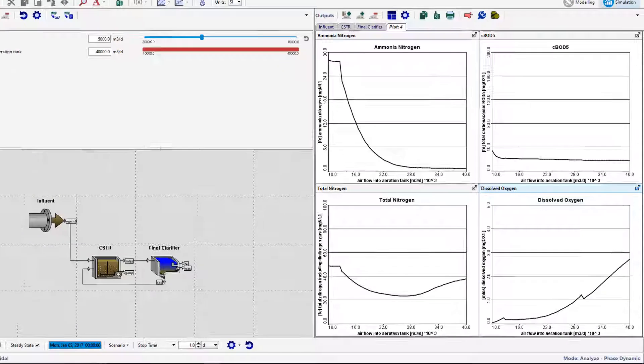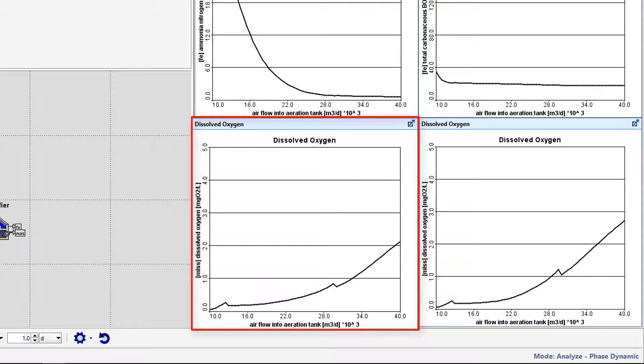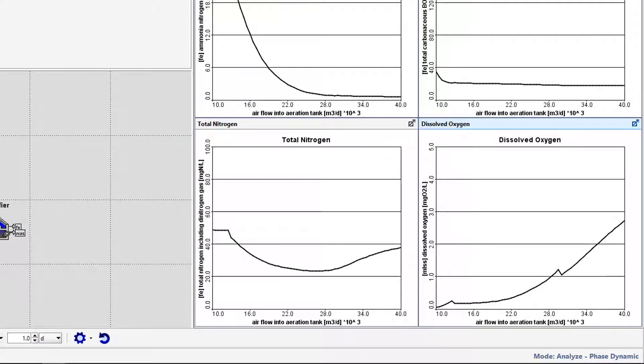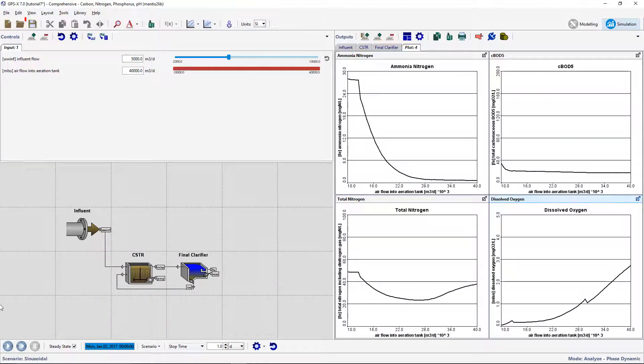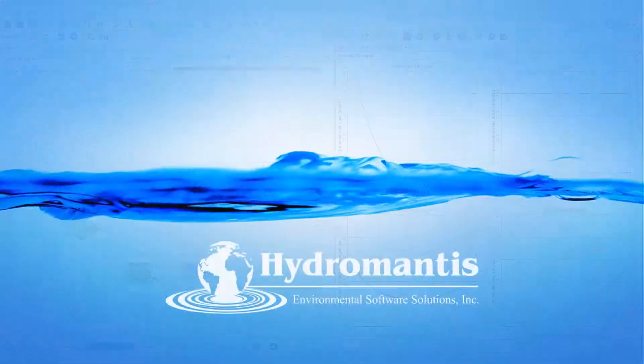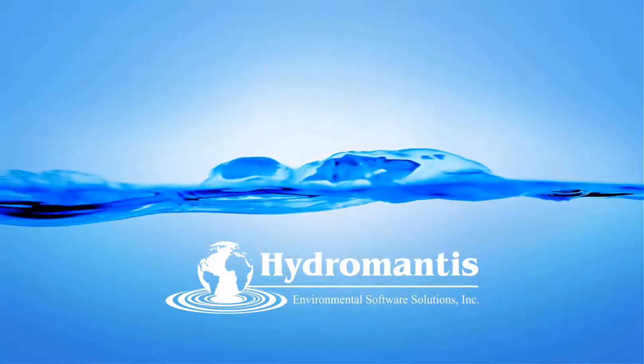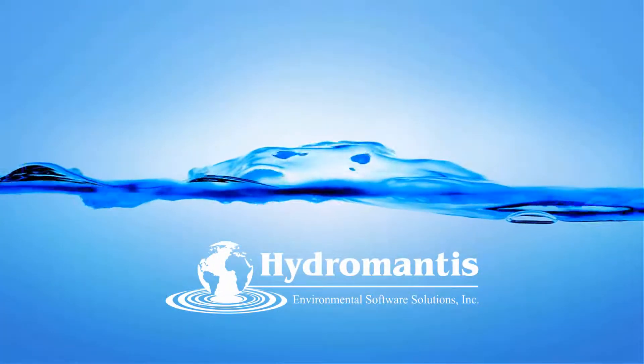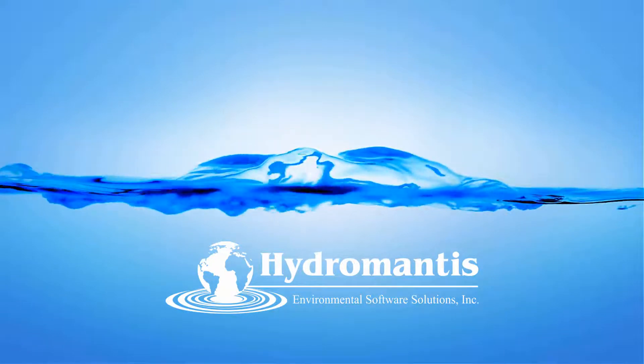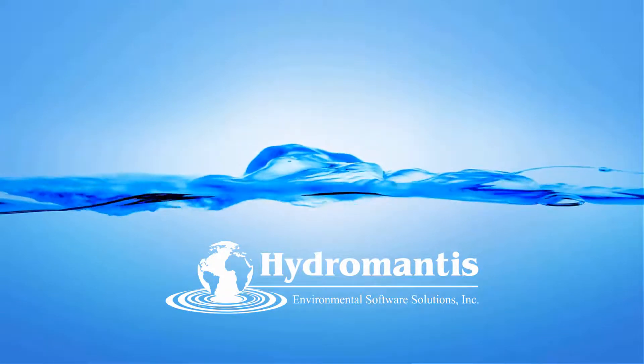This graph is only slightly different to the results presented when steady-state was selected from the Analyze menu. The graph shows the DO concentration after 1 day for an airflow of 10,000 to 40,000 m3 per day, as opposed to showing the steady-state value at time equals 0 when carrying out the steady-state analysis. Save your layout. You have now completed tutorial 7 and should be familiar with using the Analyze function in GPS-X in its use in performing sensitivity analysis.